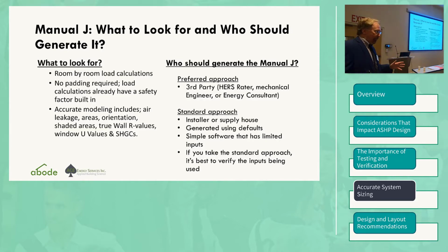What we tell builders is, you've got a model home that you're building everywhere, right, like a box colonial - one of our builders does 100 a year of these box colonials. So make sure you know what the heating load of this house is, and then you can go to the HVAC contractors and say, here's my heating and cooling loads, give me a system for that. If you go straight to the HVAC contractors and just say here's a house plan, you're going to get an HVAC system that's probably 150 to 200% higher than what you really need. That's just what happens, it's still happening. Really, the best way is for the builder to spend $500 doing a Manual J right up front for each model, get it right, and then get quotes from HVAC.